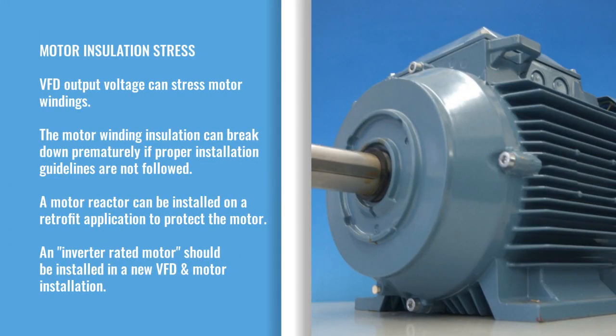Motor insulation stress is another drawback. VFD output voltage can stress motor windings, and the motor winding insulation can break down prematurely if proper installation guidelines are not followed. A motor reactor can be installed on a retrofit application to protect the motor, and an inverter-rated motor should be installed in a new VFD and motor installation.